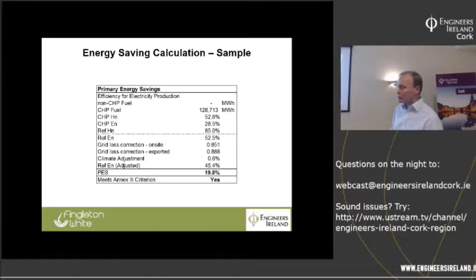The climate adjustment, the reference value for electricity generation is based on a standard temperature of 15 degrees. For every degree you go below that, you add on 0.1% efficiency to correct for that, because in colder climates you get better efficiency from the plant. So that gives you your reference value here. And then you get primary energy savings of 19.8%, and you're over the 10% threshold, so that works very well.